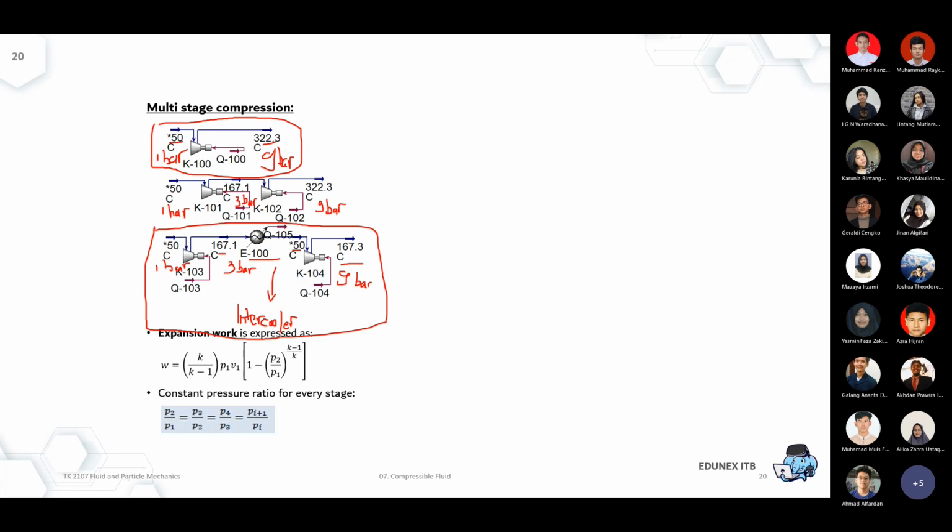High temperature spec matters, because steel also has different grades. Steel for 150 degrees C is a different grade from steel for 300, 400 degrees C. But multi-stage compression becomes almost meaningless when you don't have any intercooler. Well, at this point I will say almost meaningless.